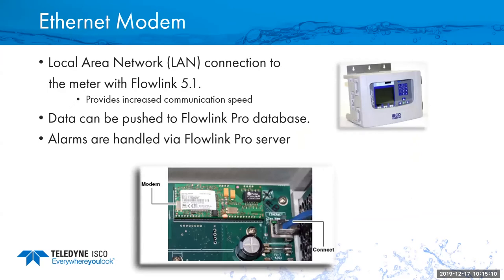An Ethernet modem is a way for you to connect the signature meter into your network. So then you can use the signature meter Ethernet modem to connect with FlowLink via TCP connection. So what you would do is you would type in the IP address of the signature meter on your network and be able to connect into it and retrieve the data. If you have a FlowLink Pro database already on your network, you're able to push the data from the signature meter at intervals that you set, and any alarm conditions can also go to the FlowLink Pro server to be sent out via email or text from that server. So it just provides you a way of getting your information out without having to visit the site to download the data.